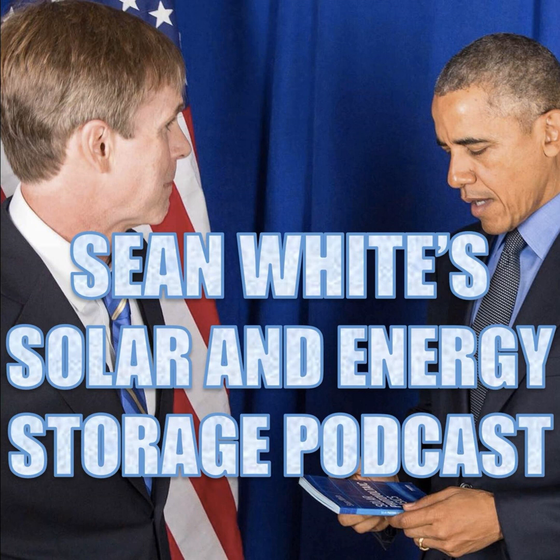And so these grounded inverters, which were the main type of inverter way back in the day, say maybe 10, 15 years ago, and before that, most inverters were grounded inverters. And that was a type of grounding that I like to call fuse grounded. So these fuse grounded inverters, what they did is they did some system grounding that's on the DC side of the inverter, and they would connect usually the negative, but sometimes the positive conductor coming from the array to the grounding bus through a fuse in the inverter. And then if enough current went through a fuse, that was a very clever way of determining that there was a ground fault. Very clever, but maybe not sensitive enough.